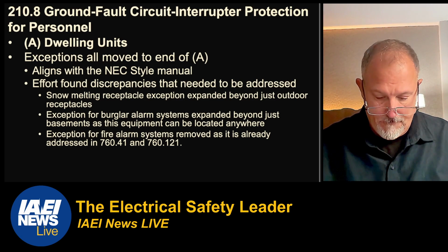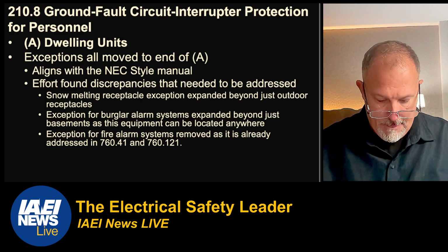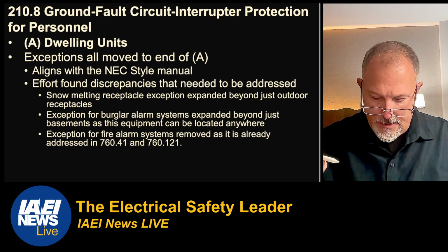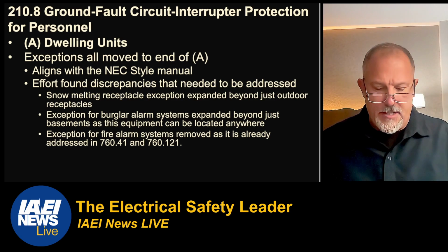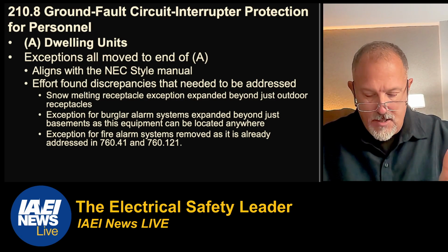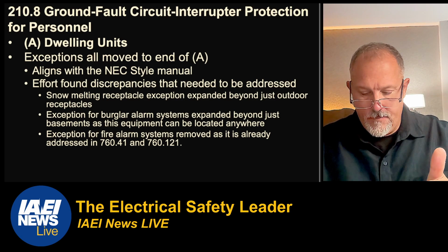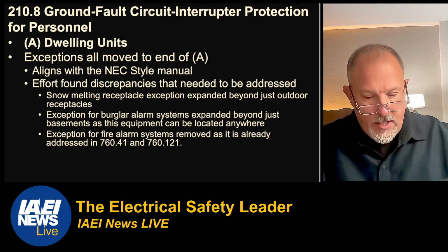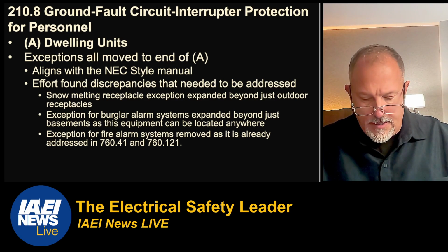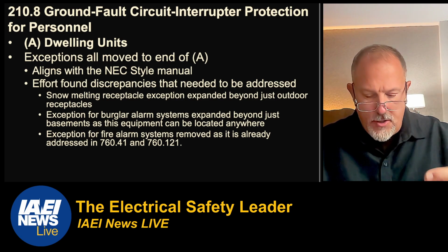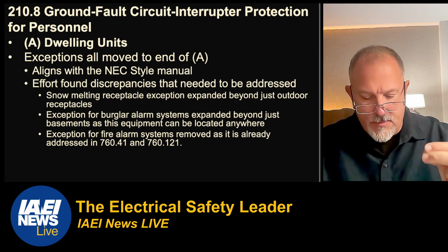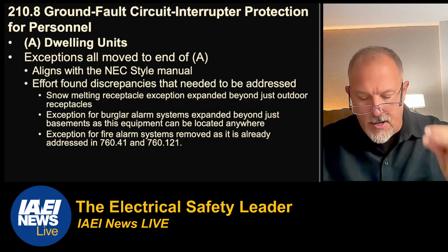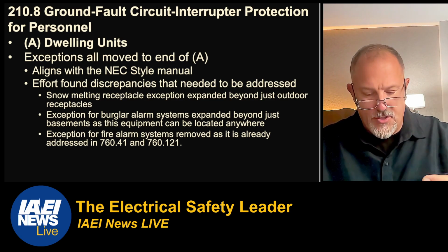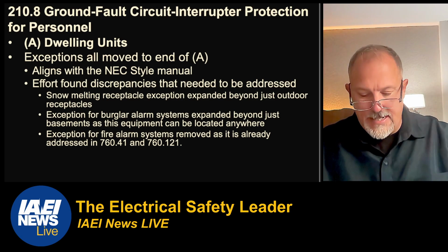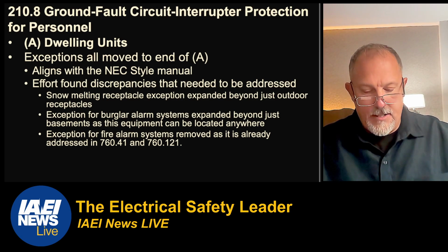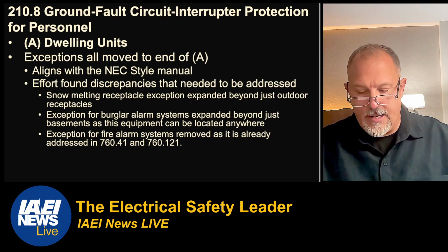There was another one. Yeah, that was the other one. Exception number 1. Remember the exception for readily accessible. And we expanded that, I think, for snow melting, de-icing. So it's receptacles that are not readily accessible and are supplied by a branch circuit dedicated to electric snow melting, de-icing, or piping and vessel heating. Shall be installed in accordance with 426.28 as applicable.